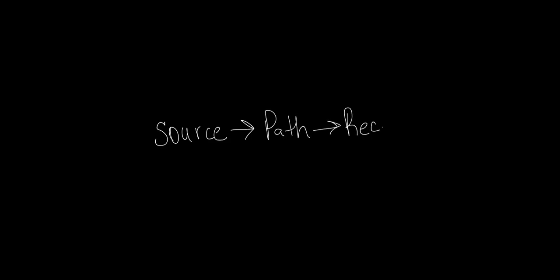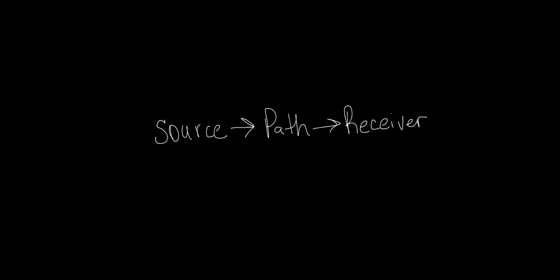To do this, an accurate acoustical model must be generated. AHRI Standard 885 specifies the source path receiver process to model the end noise that any occupant might hear. Let's look at how this can be done.